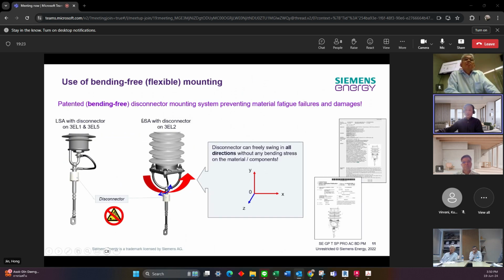For this design, NGLA, this is also well known for fatigue problems, because the disconnector is a necessary mandatory element. If the surge arrestor is failed, then we should cut off the permanent grounding point here. Then the disconnector should separate the circuit. But the mechanical part of the disconnector will also face mechanical fatigue failures, because on the towers, under the wind position, under the high vibration situation, there is a lot of fatigue effect on the disconnector. And in some cases there will be incorrect installation of the grounding cable, because it will be connected to the grounding cable, then the disconnector is always under mechanical tension. It will lead to even heavier fatigue failures.